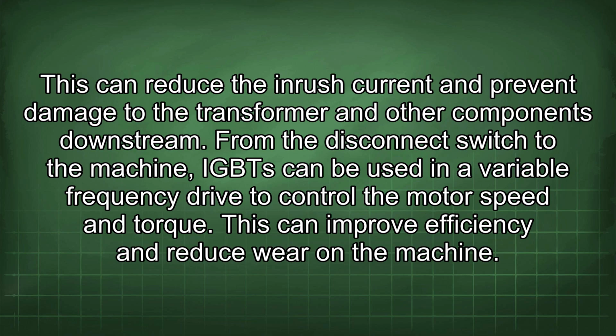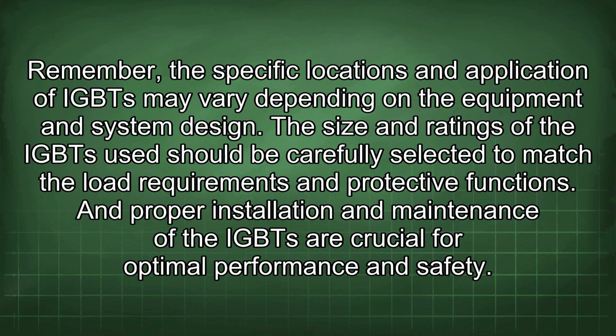From the disconnect switch to the machine, IGBTs can be used in a variable frequency drive to control the motor speed and torque. This can improve efficiency and reduce wear on the machine. Remember, the specific locations and application of IGBTs may vary depending on the equipment and system design. The size and ratings of the IGBTs used should be carefully selected to match the load requirements and protective functions. And proper installation and maintenance of the IGBTs are crucial for optimal performance and safety.